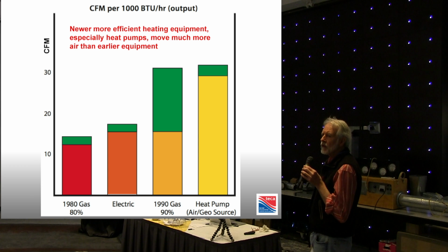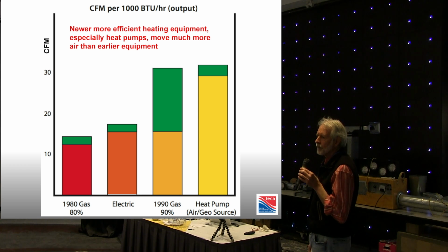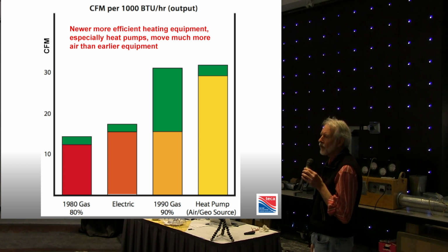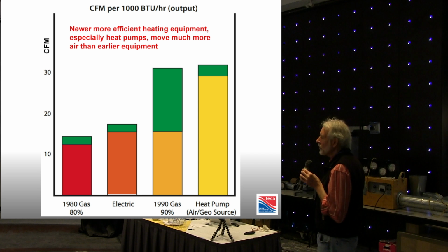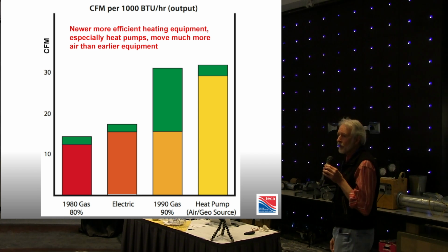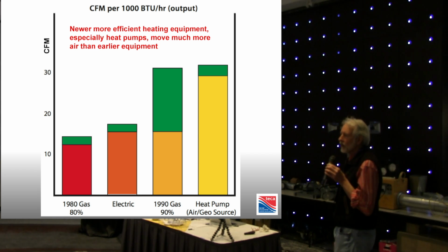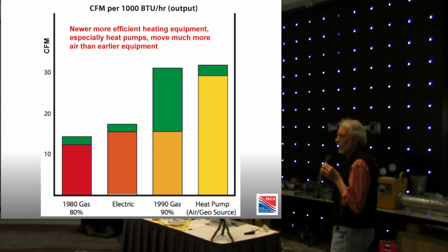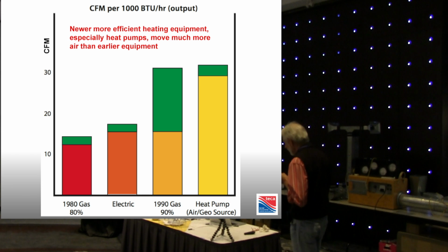But I said, you can ignore reality. You can ignore reality if you have enough money behind you. But you cannot ignore the results of reality. The simple fact of life is if you put a heat pump into the older duct systems and you match the output of what you had with a heat pump of the same capacity, you will destroy them.